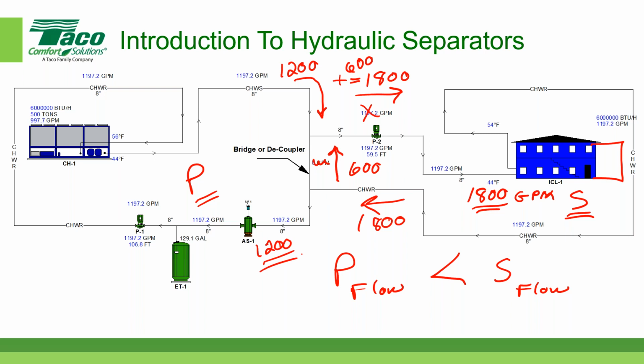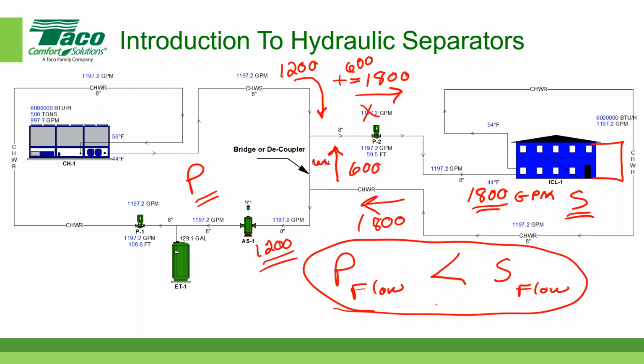And that's the case when the primary flow is less than the secondary flow. And that's the third case. The important thing to keep in consideration is whenever the primary flow is less than the secondary flow, the flow across the bridge is in reverse. It goes in the opposite direction. There's a lot going on in that bridge at different times. Yeah, that's a busy bridge.